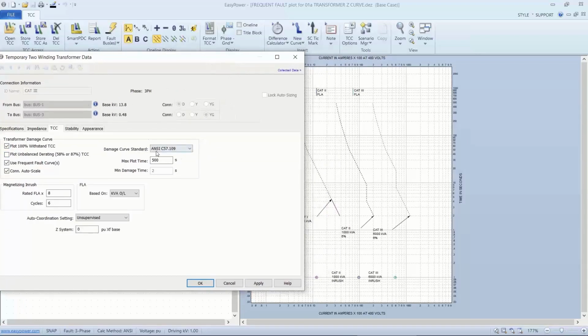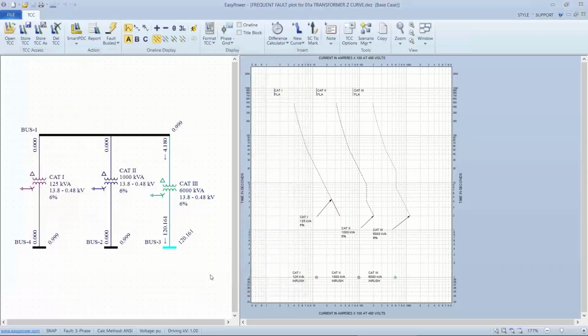Let me check a couple more keystone points. We'll talk about the unbalanced derating here in a second. We'll talk about magnetizing inrush in a second. The damage curve is again plotted on a certain range, and right here we're showing it from 2 seconds to 500 seconds. The maximum range on the current is, well, let's take that a step back. Right now we're plotting everything at 480 volts, so all these currents are referenced to a fault on the 480 side.